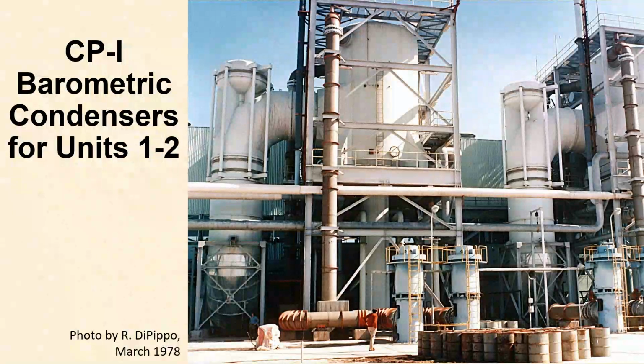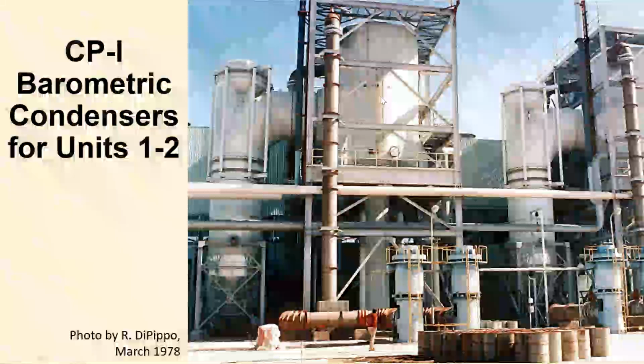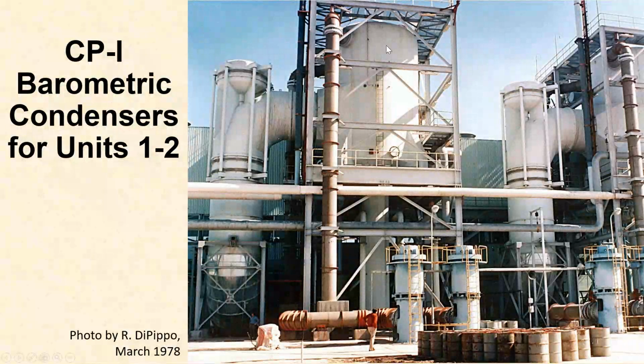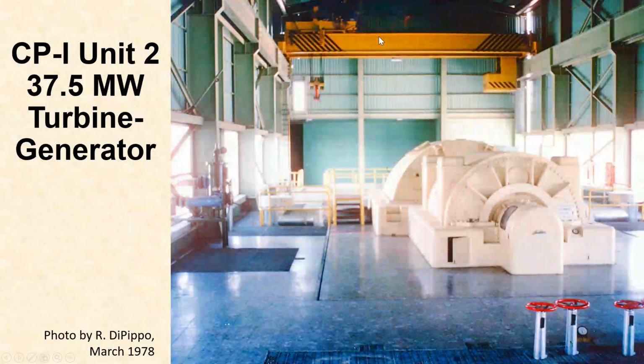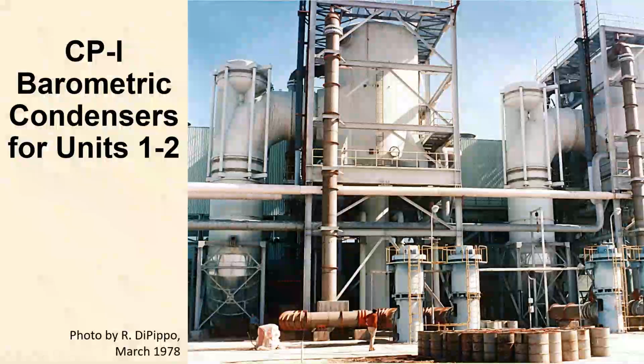This is what those condensers look like. They're very tall. They rely on the principle that atmospheric pressure will raise a column of water about 10 meters, and above that column is essentially a vacuum. Over on the left side here, you can see the exhaust from the turbine brought up and discharged into the upper section of the condenser, in which cold water is sprayed through the top. Now, these are the pumps that pull the cooling water from the cooling tower pits and discharge it here. So you get this mixture. The next slide, go ahead, next slide.